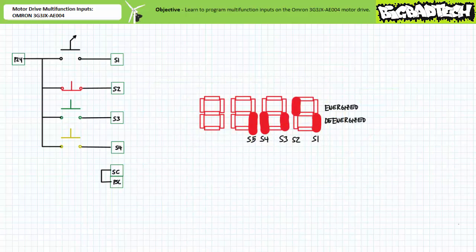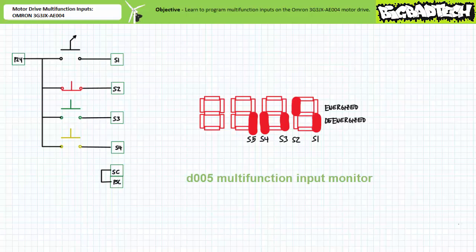Before we bring this lecture to a close, allow me to demonstrate an extremely handy feature on the OMRON 3G3JX AE004 motor drive — namely remote input monitoring. Given the input devices may be remotely located or otherwise inaccessible, this motor drive allows the means of directly monitoring and displaying the status of the five inputs. A technician does so by navigating to monitor or display function D005, multifunction input monitor. The data display will show five digital indicators; right to left, these represent the status of inputs S1 to S5. The top half of the display means the input is energized, and the bottom half means the input is not energized. Given the input wired to S2 is normally closed, note this drive in its deactivated state would show S2 as energized.